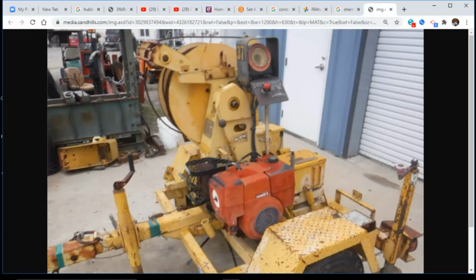So you strung your conduit, you pulled a rope in your conduit with the string. Now you take your rope and you attach it to this pulling cable, and you pull the pulling cable back through with the rope. Then you attach the cable that you're pulling in to this pulling cable on the machine. It's called a Sherman and Reilly Underdog.